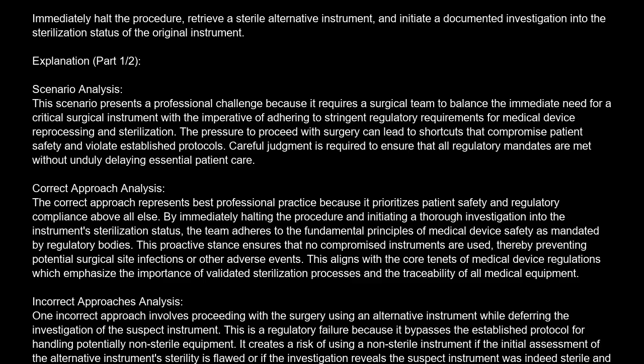It creates a risk of using a non-sterile instrument if the initial assessment of the alternative instrument's sterility is flawed, or if the investigation reveals the suspect instrument was indeed sterile and the alternative is now unavailable. Another incorrect approach is to assume the instrument is sterile based on its appearance and proceed. This is a critical regulatory and ethical failure as it disregards the fundamental requirement for validated sterilization processes. Visual inspection alone is insufficient to guarantee sterility, and this assumption directly violates guidelines that mandate documented evidence of successful sterilization cycles.